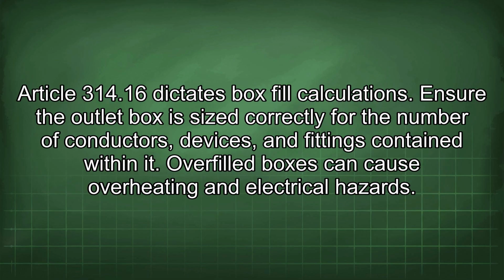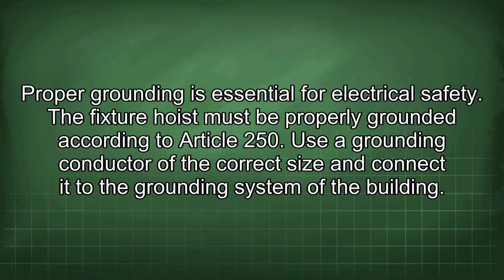Article 314.16 dictates box fill calculations. Ensure the outlet box is sized correctly for the number of conductors, devices, and fittings contained within it. Overfilled boxes can cause overheating and electrical hazards. Proper grounding is essential for electrical safety. The fixture hoist must be properly grounded according to Article 250. Use a grounding conductor of the correct size and connect it to the grounding system of the building.